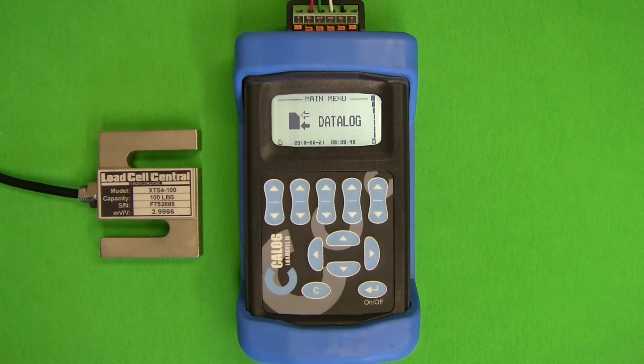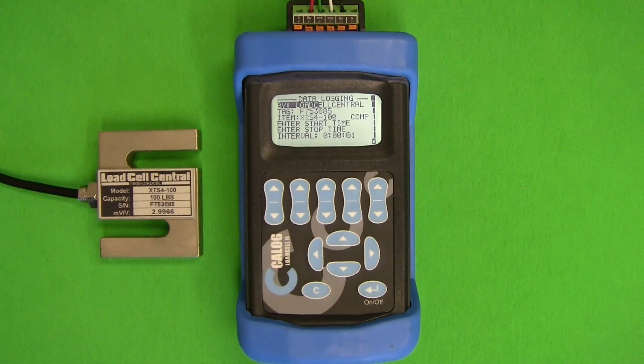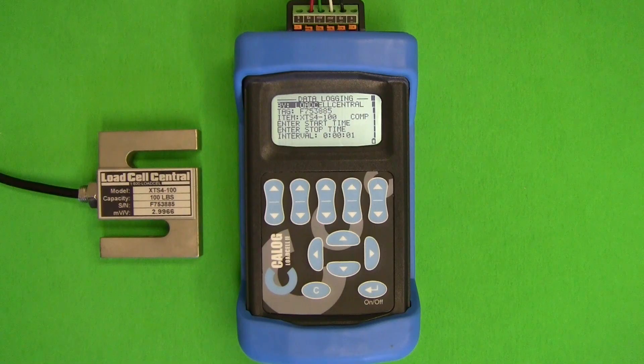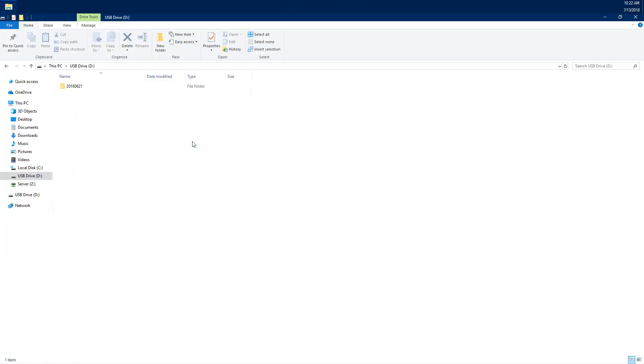The Calog is capable of data logging to the included microSD card. Under data logging we can set file names, descriptions, and intervals. In order to create a log file we must set the proper start and end times for our test, then enter the load cell display screen. This will automatically create our file and log for the duration selected. Once our CSV file has been saved we can open it in Microsoft Excel where we can perform data analysis.